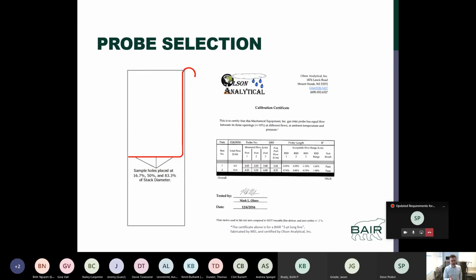If you don't have a test port and you are intending to use a 3-point long line or a rake probe, you can go over the top, as you can see here on the left. Again, you would want to have a rake probe that is professionally designed. The holes on the rake probe are different sizes to accommodate the flow criteria for these, and so they're certified to show that you've got uniform flow through each of those holes on a 3-point long line. So all that to say, if you see someone that pulls a piece of stainless steel tubing in the field and drills 3 holes in it quickly, pinches one end of it and ties it into other tubing and throws it over the stack, I would question whether or not that meets the criteria.